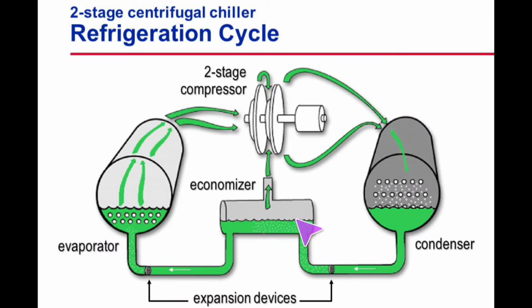All the brands use some form of carriers. It's real common to use those brazed plate heat exchangers for their economizers. So anyway, it's all the same basic function. Yes, you lose capacity, you gain efficiency. Vapor gets pulled back into the compressor.